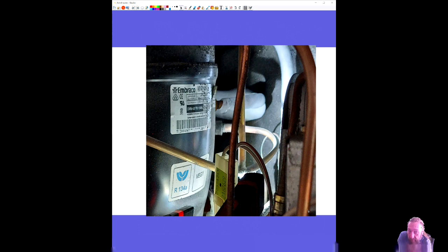Okay, right, Jonas, DW, high head pressure because it's not releasing heat. So it's going to create excessive temperatures in the condenser, which is going to raise your pressures. And in that case, that's going to affect the cooling of the fridge, but it's going to cause a bigger problem. What's going to happen within the system? Well, the de-superheating process won't happen, right? So it's not going to fully turn back to a liquid. It's gonna work harder. The compressor probably overheated. Yeah. Too much strain on the compressor.